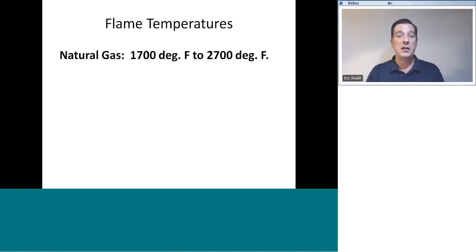When we are talking specifically about fuel burning appliances in a residential or commercial application being used as a heating fuel, I'm really being specific because I want to differentiate between other uses of natural gas in industrial applications, such as in forges or kilns or welding or flame spray type operations. That's a whole other story. But in space heating and process heating applications in residential and light commercial applications, our natural gas flames are going to be in the 1800 to 2000 degree neighborhood. So write that down in this vicinity, 1800 to 2000 degree flame temperature for natural gas.